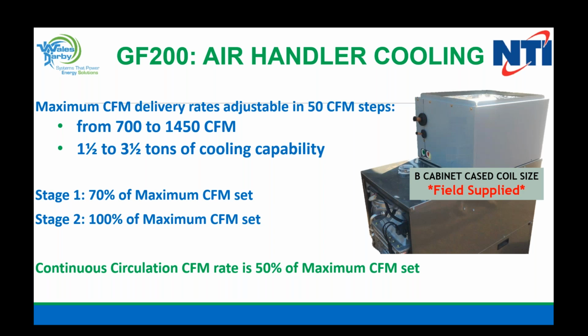So if you put in a unit with a 2-stage outdoor compressor, your first stage is going to be about 70% of the maximum CFM, and then at stage 2, we'll go up to 100%. And again, that is field adjustable. So the blower does react to static pressure, and it reacts pretty rapidly.